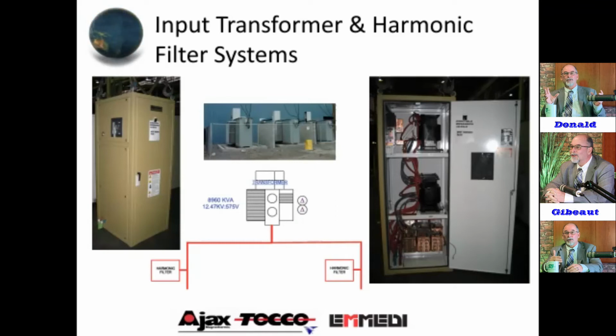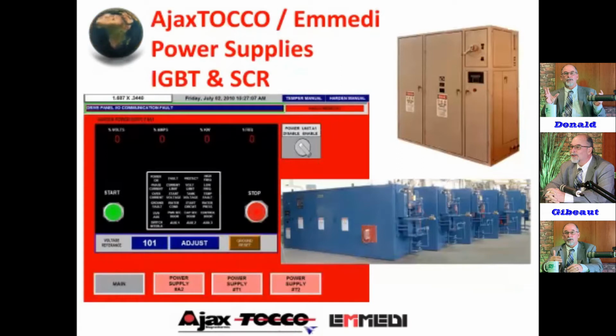The significance of this is that you don't have to have other manifolds and water drops. This bolts right to the power supply, and everything is water cooled. Some of the vaults that you saw were required on competitive equipment because they had aftermarket or other vendor harmonic filter systems standalone that were not fully water cooled. They had to air cool them, so they had to control the air in that vault for this and other things in the power. So we water cool everything, so everything's controlled, and that's the way to engineer bulletproof, as we like to say. Here shows that water system bolted onto the power supply with a heat exchanger, pump, and a little reservoir. We do, like I said, the Pacer power supplies, IGBT and SCR. Emmedi can make these power supplies to the CE rating for Europe. They also have their own power sources.